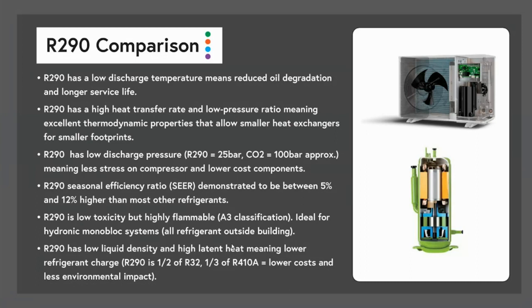R290 has a high heat transfer rate and a low pressure ratio, and I won't go into the details of what those mean, but they basically equate to excellent thermodynamic properties that allow smaller heat exchangers and smaller footprints. That allows R290 appliances to be compact and produce very good performance for the size of the unit. R290 has a low discharge pressure, as we mentioned before, comparing it with, say, CO2. R290 has a pressure in the compressor of about 25 bar. Compare that with CO2, which is 4 times higher. So 100 bar means a lot of stress on the compressor. R290 compressors have less stress for longer service life, and they have lower cost components because they don't have to deal with those very high pressures.